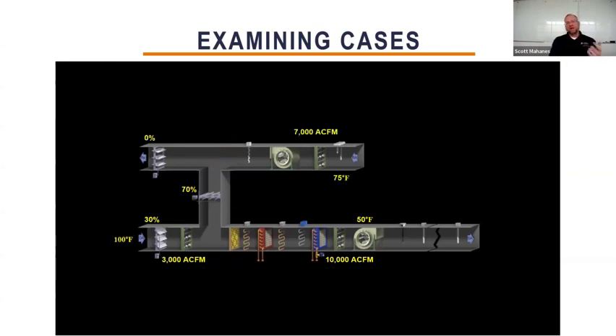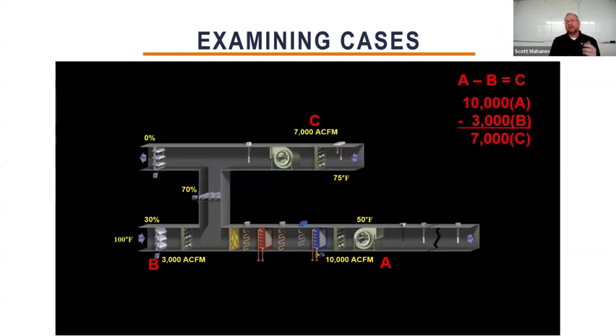We also do comparative tests with supply, return, and outside air, often like an ABC sort of test. If A is the supply, B is the outside air, and C is the return, and I expect to have no relief because the relief damper is closed, then we think that A, 10,000, minus B of 3,000 should yield a result of 7,000 on C. And in fact, it shows that right now. And normally we would say this looks good. But you have to do it from a mass flow perspective and not volume.